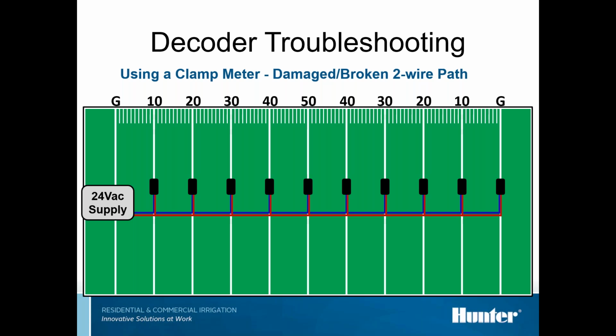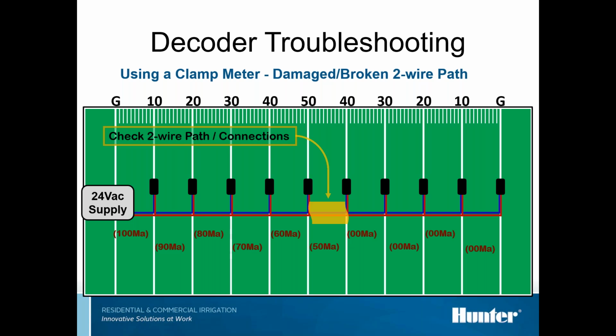Damaged or broken 2-wire path. Typically, after a damaged, broken 2-wire path, you're going to lose everything past that point. And you'll see something representative of this. You're going to have numbers that drop incrementally until you get to a point where suddenly you get zeros. So in the section between 2 decoders, where it went from a normal reading down to 0, either your red or your blue or both wires have been damaged and need to be repaired. And that's where using your ground fault indicator comes in very handy.